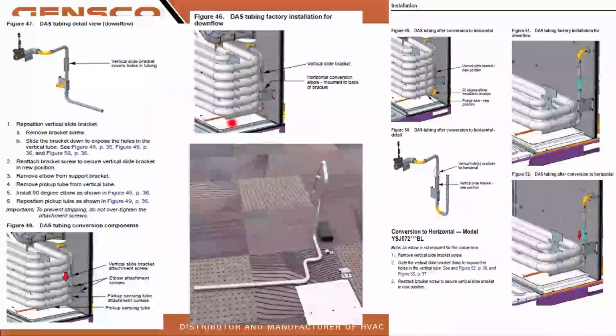Downflow, it's going to be set up like this. So if we are converting it to horizontal, there will be a horizontal application because our ductwork's going to come out. I do know a few of you have some horizontals going in, but you're going to rotate that and put it upwards into the airstream. Again, this is just a sampling tube that the actual wires are mounted up in here and inside the evaporator control, and it is insulated in there.